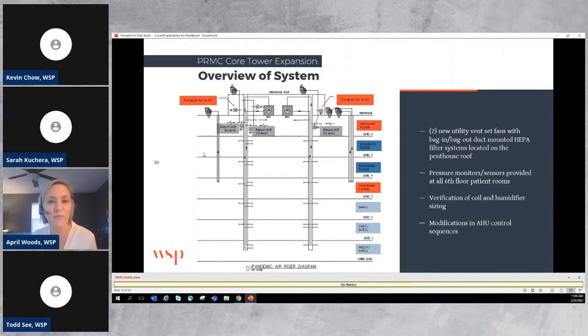We went ahead and provided new utility vent set fans with bag in, bag out filters, HEPA filters, located on the penthouse roof. Those were specific to support the 6th floor. And then we already had decided as a team and gotten direction from Parkview to design provisions for the 3rd floor to be full pandemic operation, which included putting in 3 additional exhaust fans to serve that floor, in addition to all of the shafts, which also was a pretty big change to the floor plans.